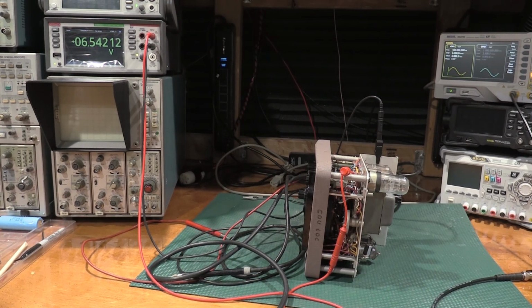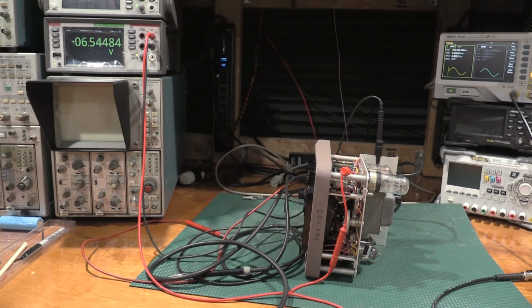And then if that hangs around at 6.3, 6.2, 6.3, we'll hook up the function generator and see if we have readings that make sense. If we do end up getting into a calibration, I'm going to have to kick on the amplifier for the 5200, because the 5200 only goes up to 100 volts and I'm going to need a 300 volt source. So we'll see what happens, but I'm starting to get excited.